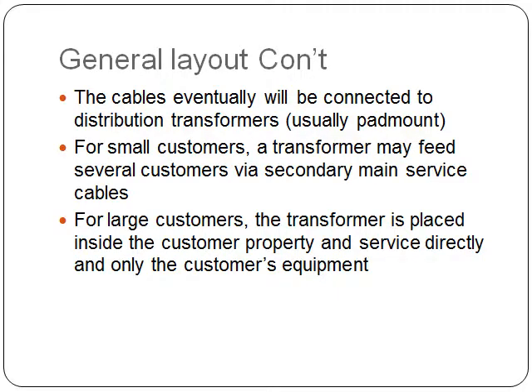The cables eventually will be connected to distribution transformers, usually in the form of pad-mount transformers. For small customers, a transformer may feed several customers via secondary main service cables. For large customers, on the other hand, the transformer is placed inside the customer property and serviced directly and only at the customer's equipment.